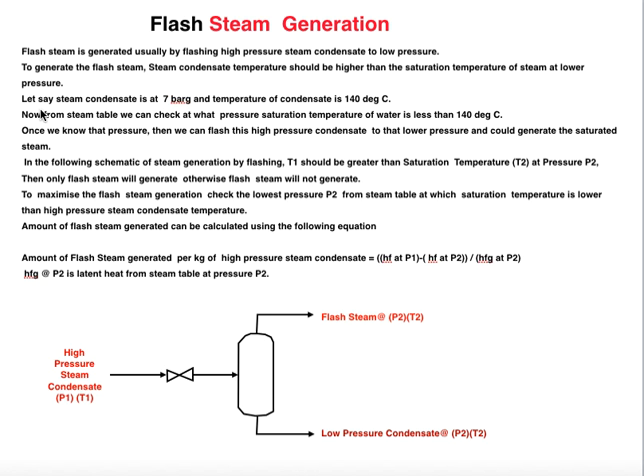Flash steam is generated by flashing high pressure steam condensate to low pressure. To generate flash steam, the steam condensate temperature must be higher than the saturation temperature of steam at the lower pressure. That is, if we have high pressure condensate at pressure P1 and temperature T1, and we reduce pressure to P2, where T2 is the saturation temperature at P2, then T1 must be greater than T2.